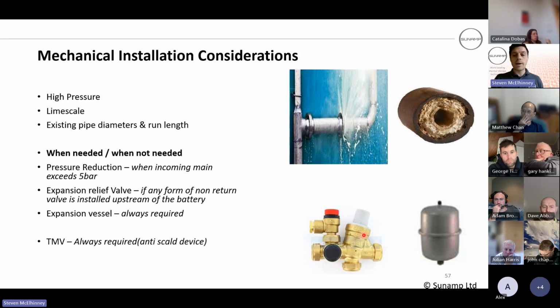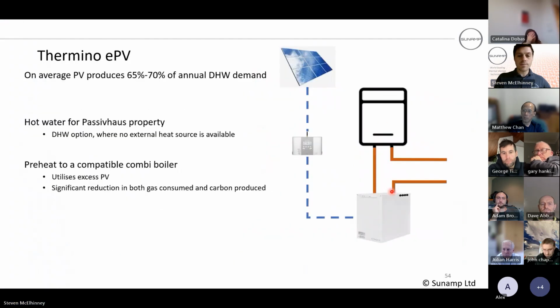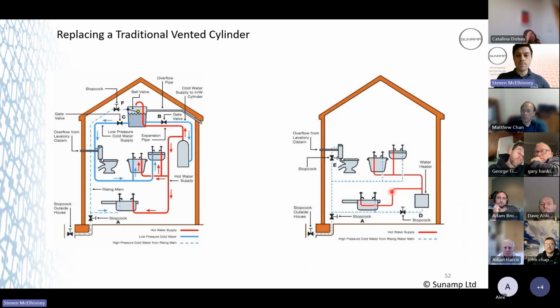So take away the manifold block for a second. You've got two separates: a separate pressure reducing valve and a separate 6 bar expansion relief valve. Say you had your pressure reducing valve at point of entry into the house. So let's go back to our interactive house. You've got point of entry, your pressure reducing valve here, and your heat battery here. You could essentially fit your expansion relief underneath the kitchen sink, teeing off the cold mains and tying into the waste there. And that's a way around it.